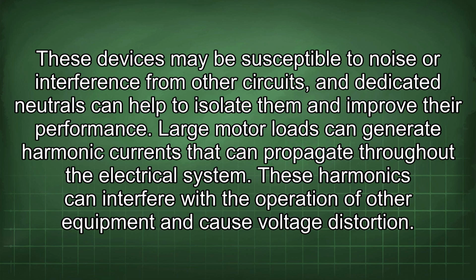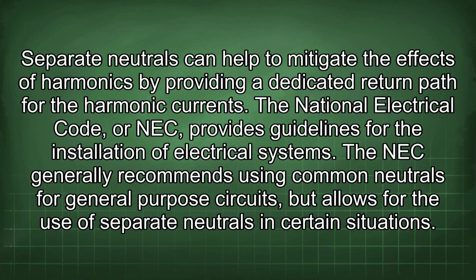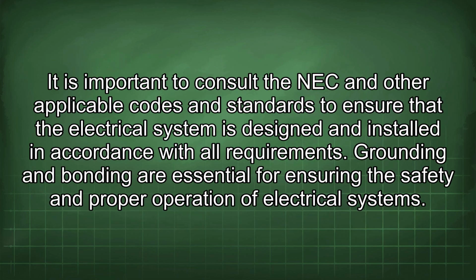Large motor loads can generate harmonic currents that can propagate throughout the electrical system. These harmonics can interfere with the operation of other equipment and cause voltage distortion. Separate neutrals can help to mitigate the effects of harmonics by providing a dedicated return path for the harmonic currents. The National Electrical Code, or NEC, provides guidelines for the installation of electrical systems. The NEC generally recommends using common neutrals for general-purpose circuits, but allows for the use of separate neutrals in certain situations. It is important to consult the NEC and other applicable codes and standards to ensure that the electrical system is designed and installed in accordance with all requirements.